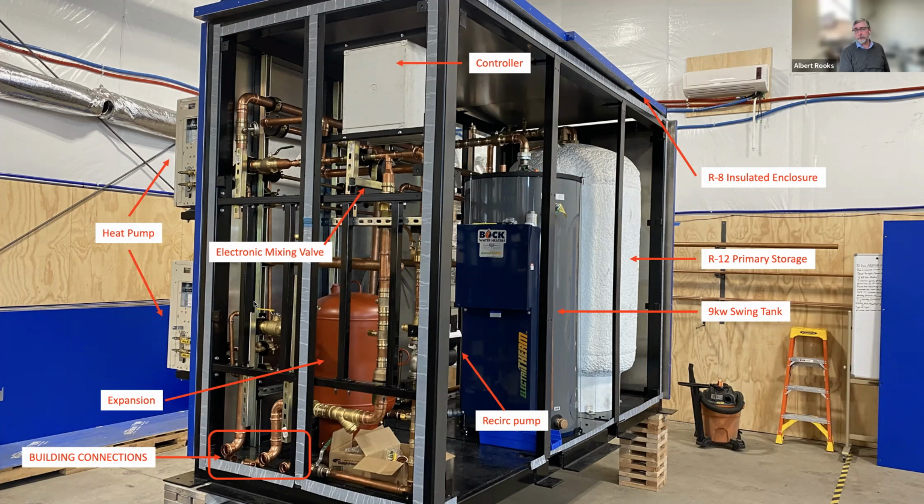So there's an annual service plan. It's pretty light: blow the coils, maybe inspect the plumbing and look for leaks, check for alarms. The controller has an alarm log. So even if you don't get notified of an alarm, it'll give you a CSV on full behavior and run cycles and things like that.